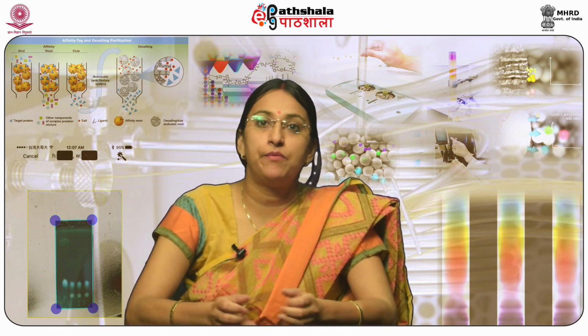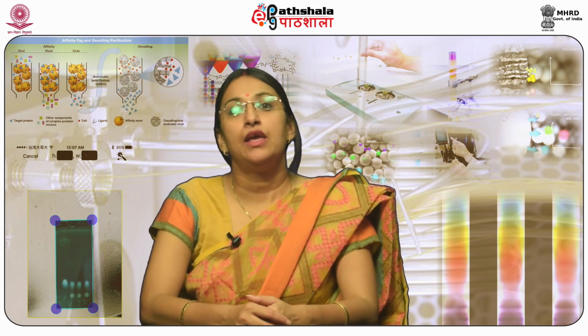This requires appropriate pressure to force the mobile phase through the compactly packed column and at the same time dissolve the analytes.